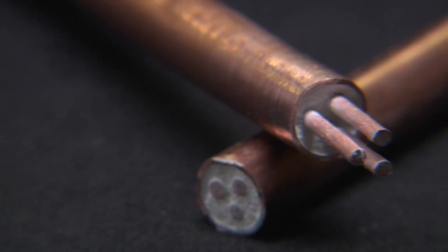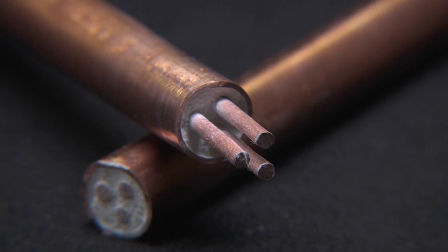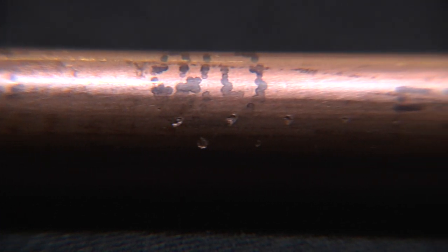In this video, we will review the proper termination procedure of a System 1850 multi-conductor MI power cable using the Pyrotenax PyroPak termination kit. Copper sheathed MI power cables are classified by UL and ULC as 2-hour fire resistive, and the improper termination of the cable can jeopardize its integrity and reliability.